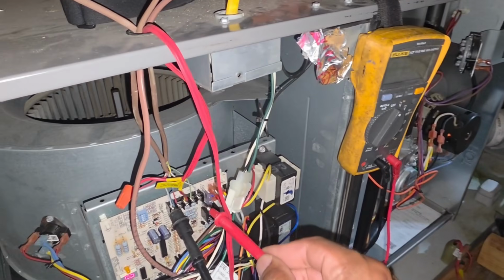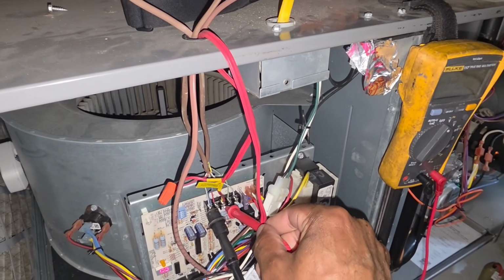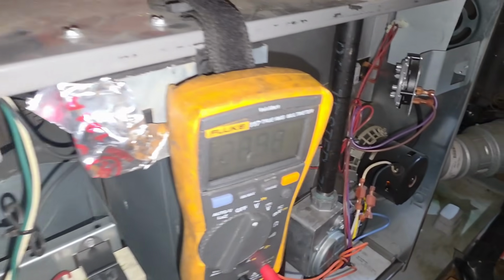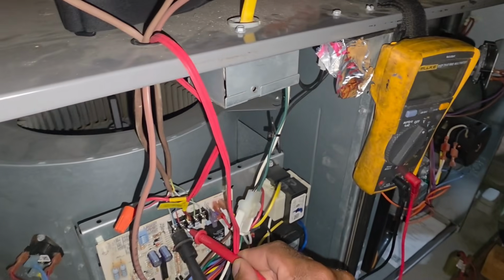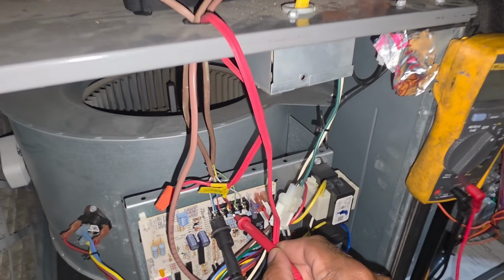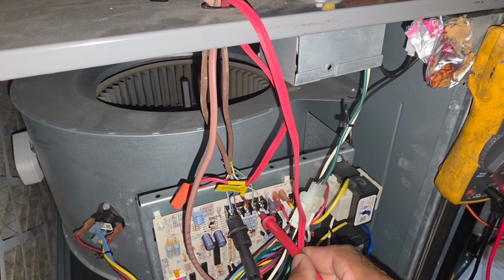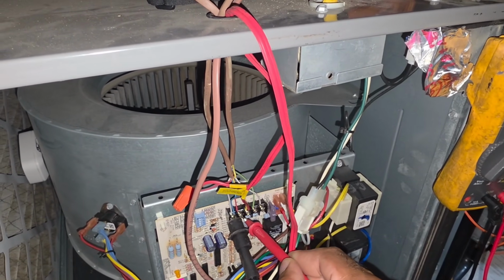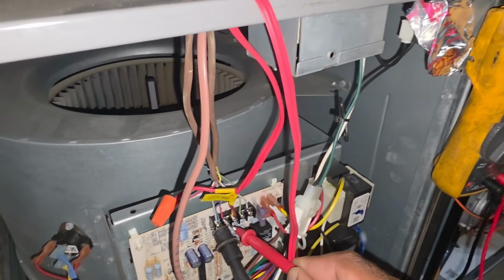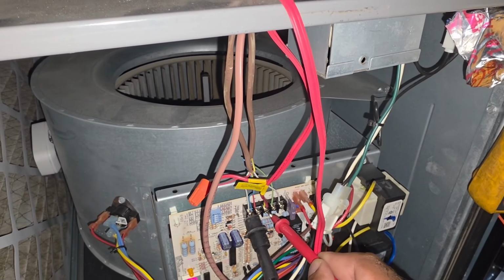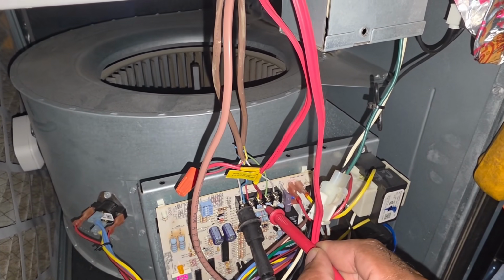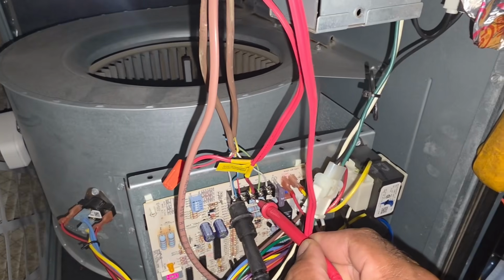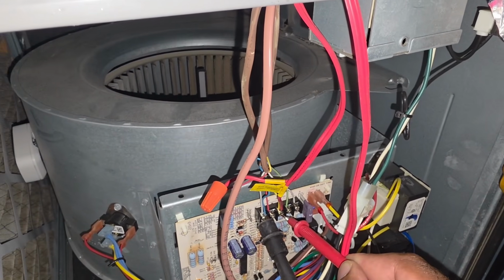The lead right here is where we're going to move around. If I put it on this red, I should get 24 volts. As you see, 24 volts. If I was calling for cool, this is my Y1 right here. You see I get 0 because it's not calling for cool. I'm looking for voltage. My system is in idle right now. So the only place I should get 24 volts is the red. If I go to Y1 and I know my thermostat is calling for it, I should get 24 volts right here. If I get 0, we know we have to continue to troubleshoot.